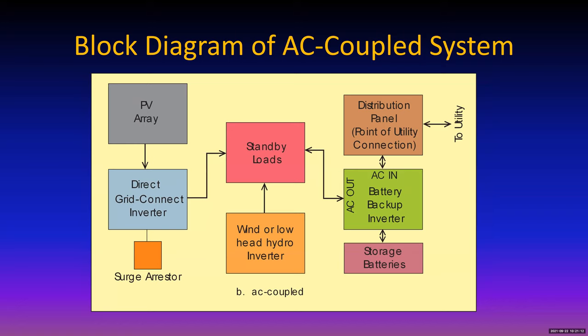This is a basic AC coupled photovoltaic system. And this can work with any other loads or any other sources as well - it can work with wind or low head hydro. What happens is you generate DC electricity and you use a straight grid connect inverter, which is a current source. But in order to be a current source, it has to use whatever voltage is desired by the standby loads. So therefore, you're producing generally 120, 240 volts electricity here.